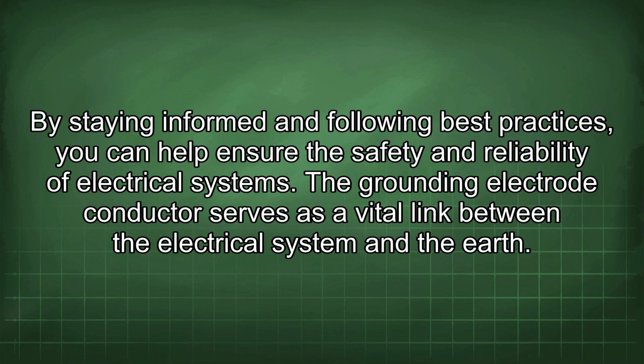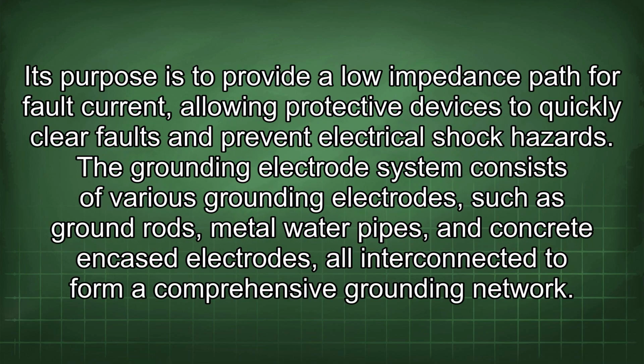The grounding electrode conductor serves as a vital link between the electrical system and the earth. Its purpose is to provide a low impedance path for fault current, allowing protective devices to quickly clear faults and prevent electrical shock hazards. The grounding electrode system consists of various grounding electrodes such as ground rods, metal water pipes, and concrete encased electrodes, all interconnected to form a comprehensive grounding network.